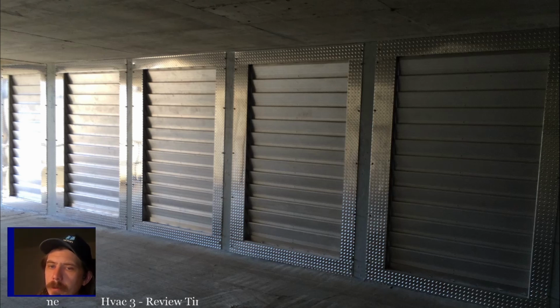So for inducer motors and things like that, you'll still see PSCs. You'll still see PSCs on older equipment and on replacements, but ECMs are becoming the standard for your small blowers, even your smaller rooftops, 5-ton. I think I've seen an ECM blower on up to a 7.5 or 10-ton rooftop. So your rooftops that don't have three-phase motors will probably be ECM motors. Your residential equipment is all moving to ECM motors.